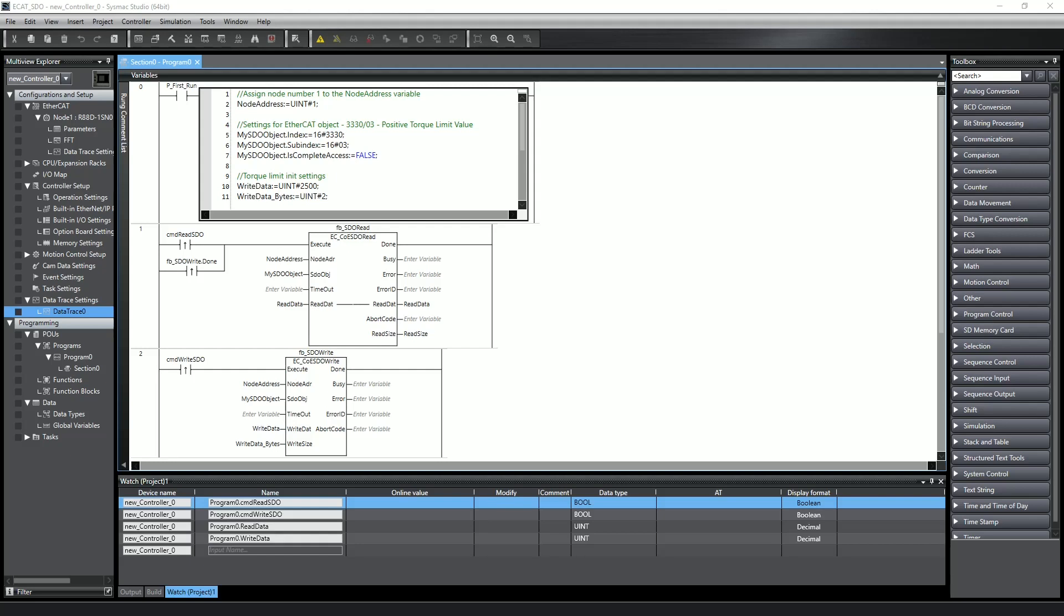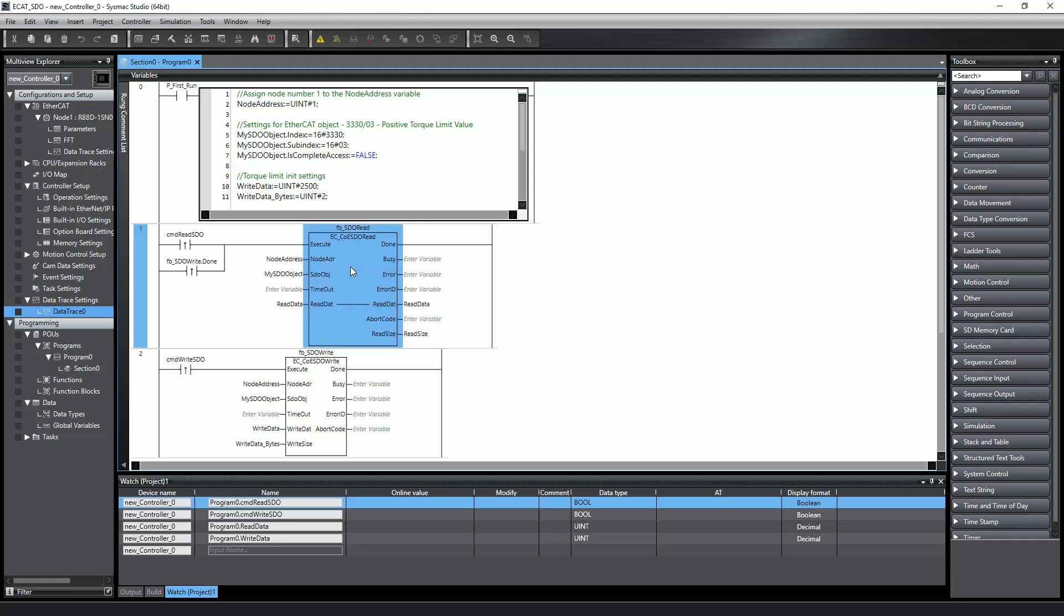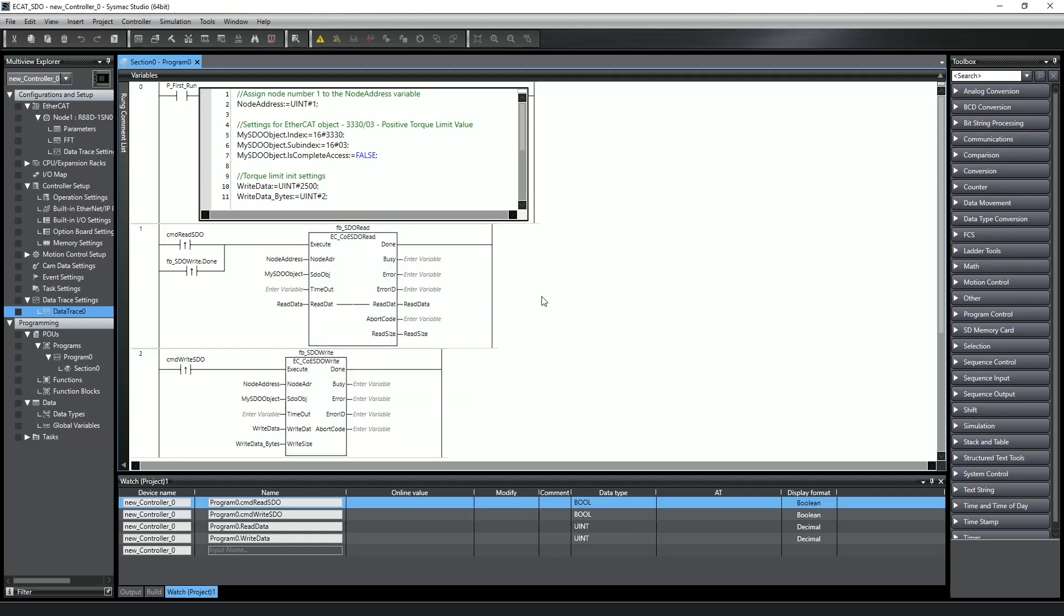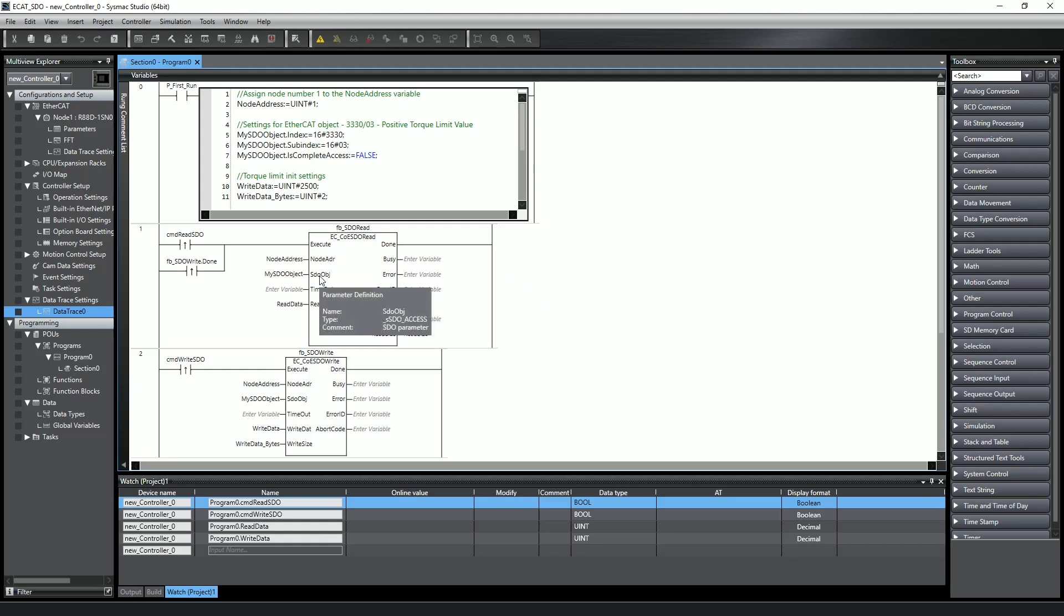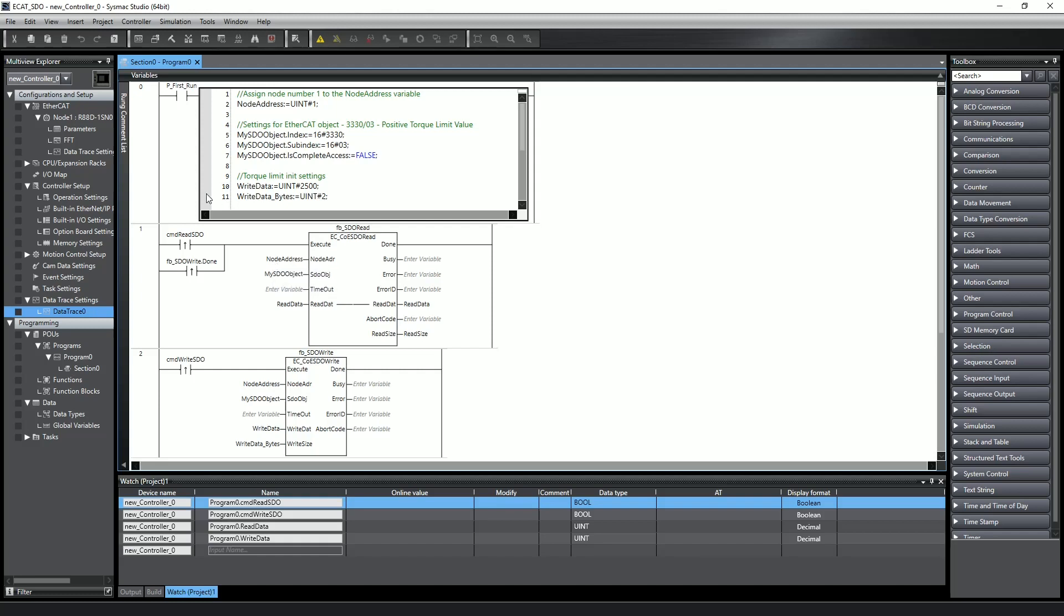Let's jump over to SysMac Studio and show how SDO communication works. This program has three rungs. The first rung contains structured text for initial variable setup on the first scan of the PLC, and then the two rungs after that contain the SDO read function block and the SDO write function block. Both the read and write function blocks have inputs for node address and SDO objects. The node address is an unsigned integer set to the value of the EtherCAT node number, and I created a node address variable to use for both function blocks.